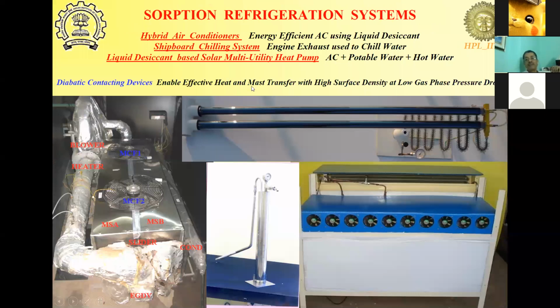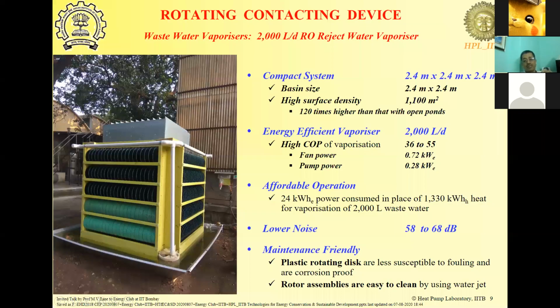Then recently, a couple of years ago, we licensed technology for rotating contacting device based wastewater vaporizers. Now, typically in an industry, wastewater is vaporized by multi-effect vaporizers, which have a thermal COP of around 3 to 4 in a 3 or 4 stage wastewater vaporizer, but they have a lot of problems with respect to corrosion, fouling, and so on. While in our case, this is operated without any heating, using ambient air itself if it is not very humid.